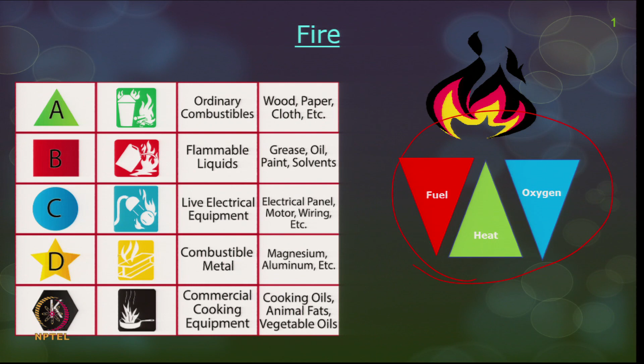There are several types of fire classification: A, B, C, D, F and K. A is primarily ordinary combustibles: wood, paper, cloth and so on. B is flammable liquids: grease, oil, paint, solvents and so on. C is live electrical equipment: electrical panel, motor, wiring and so on. D is combustible metal: magnesium, aluminum and so on. And the last one is commercial cooking equipment; all your cooking oil, animal fats and vegetable oils fall under this category.